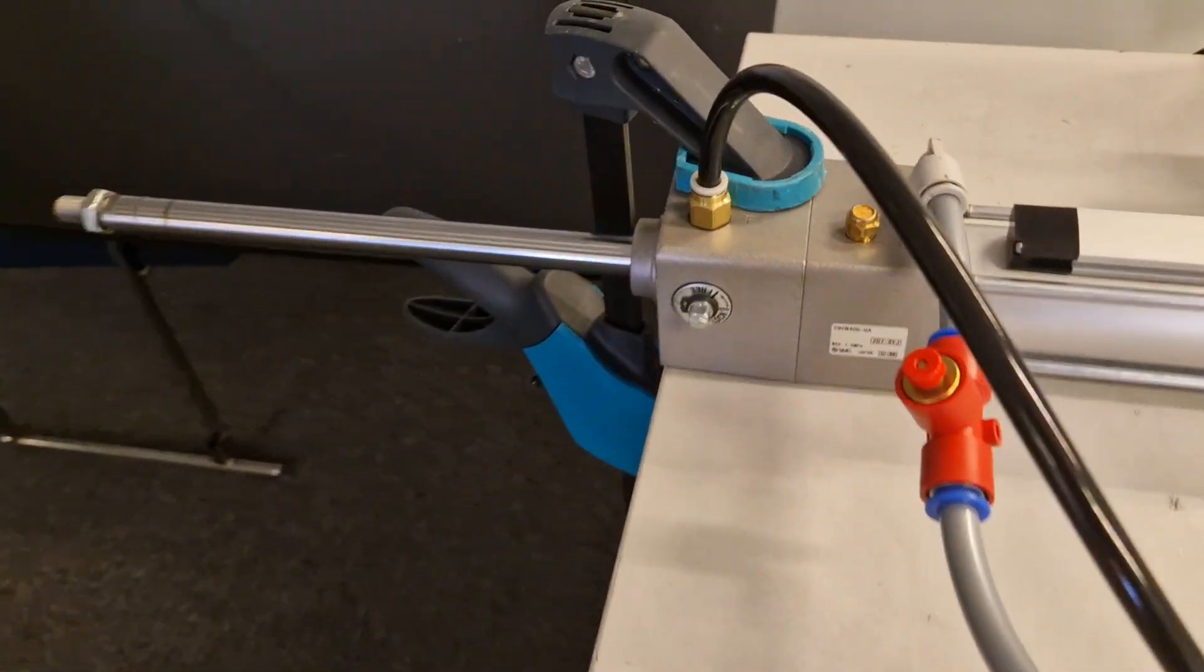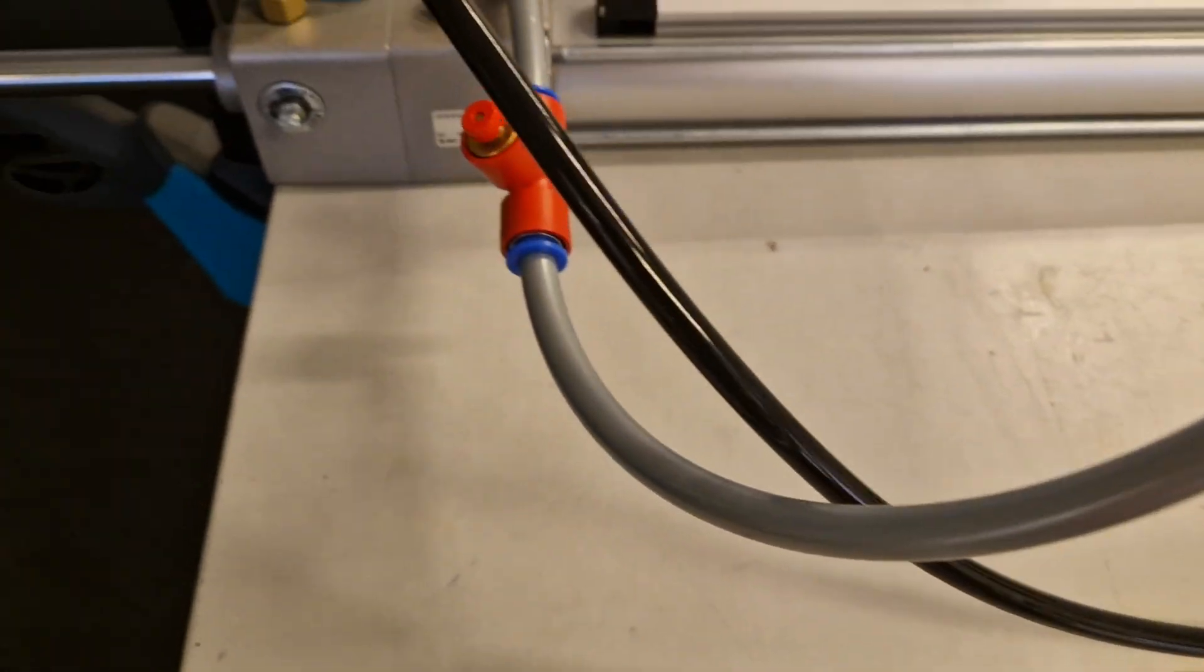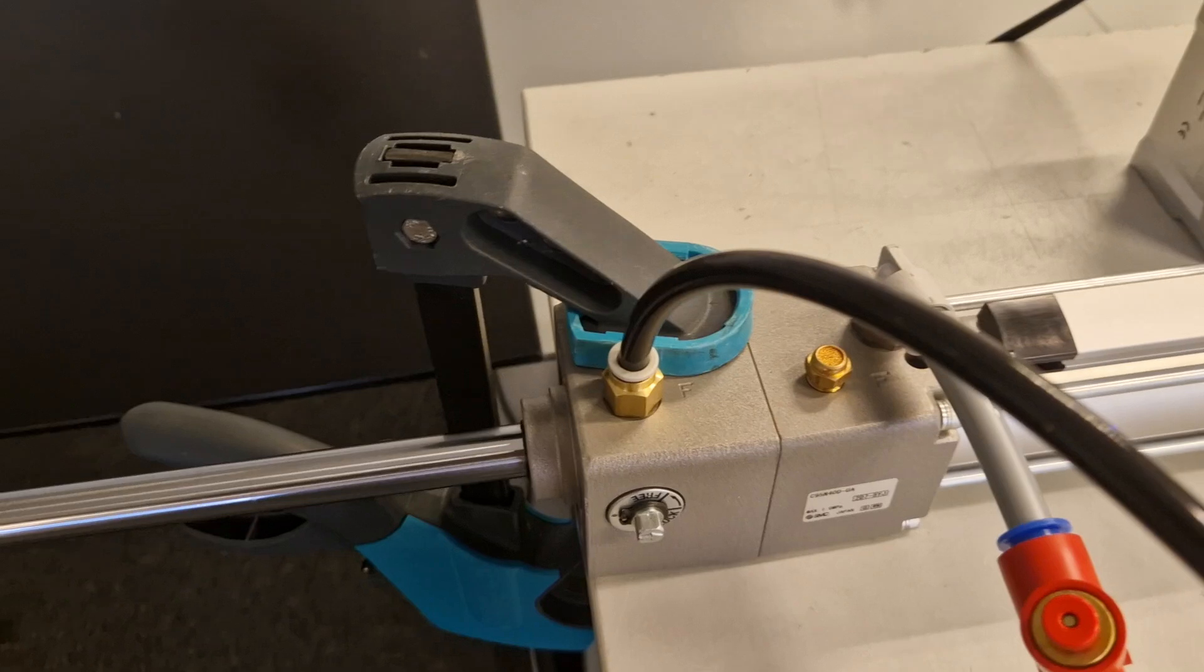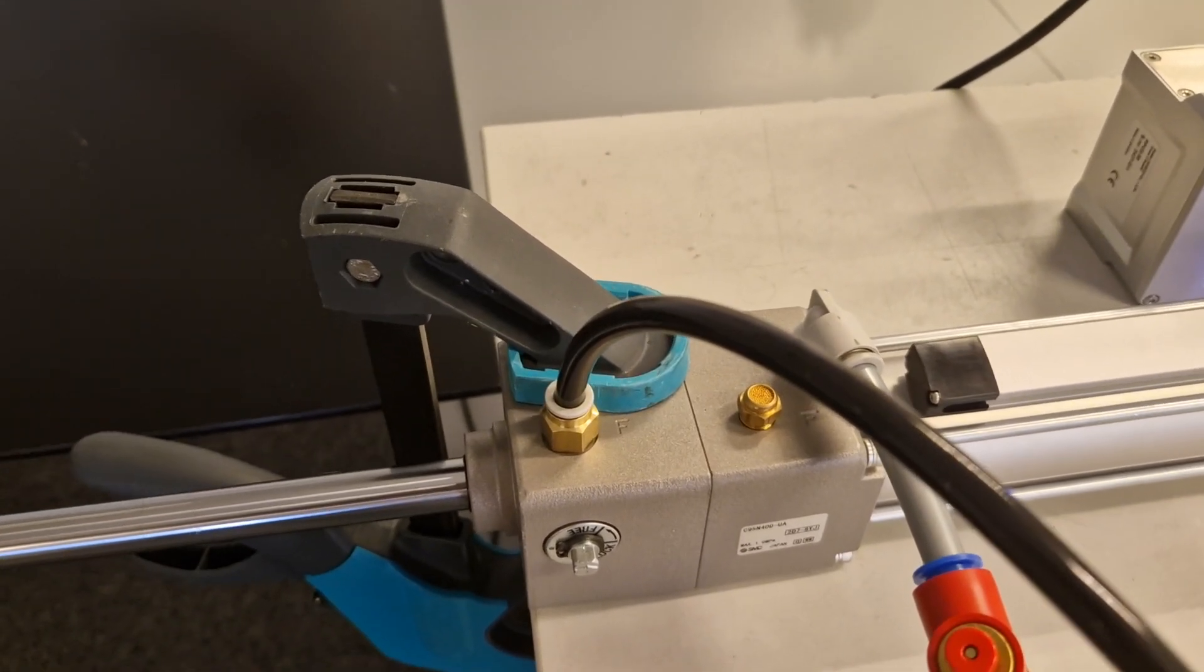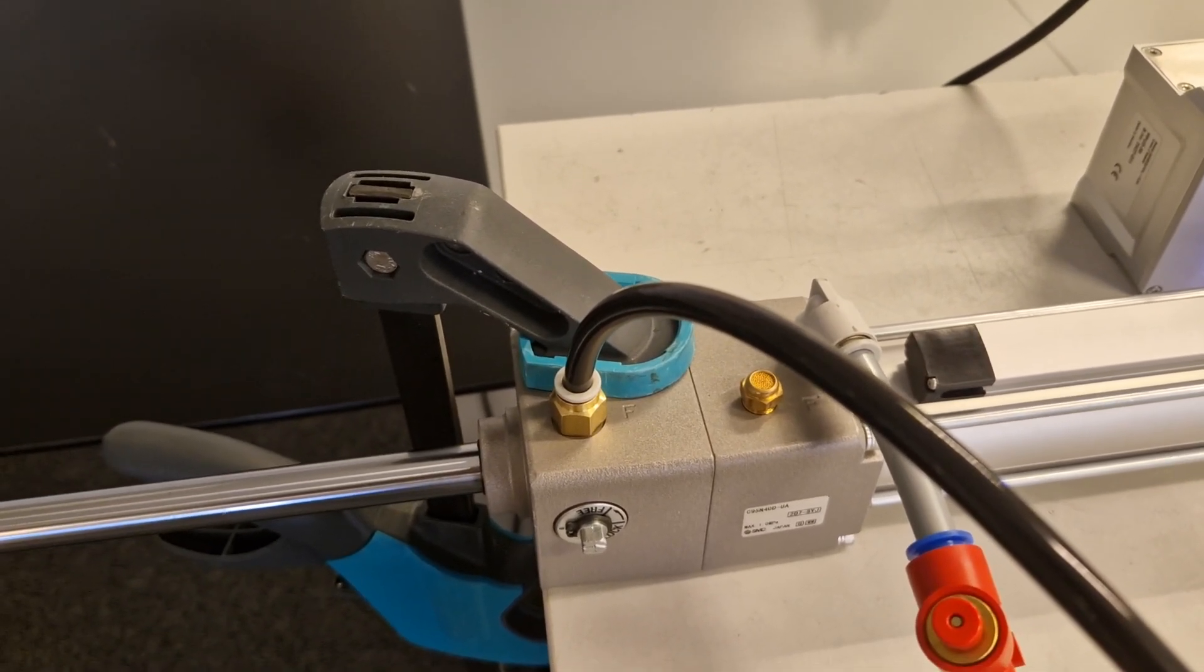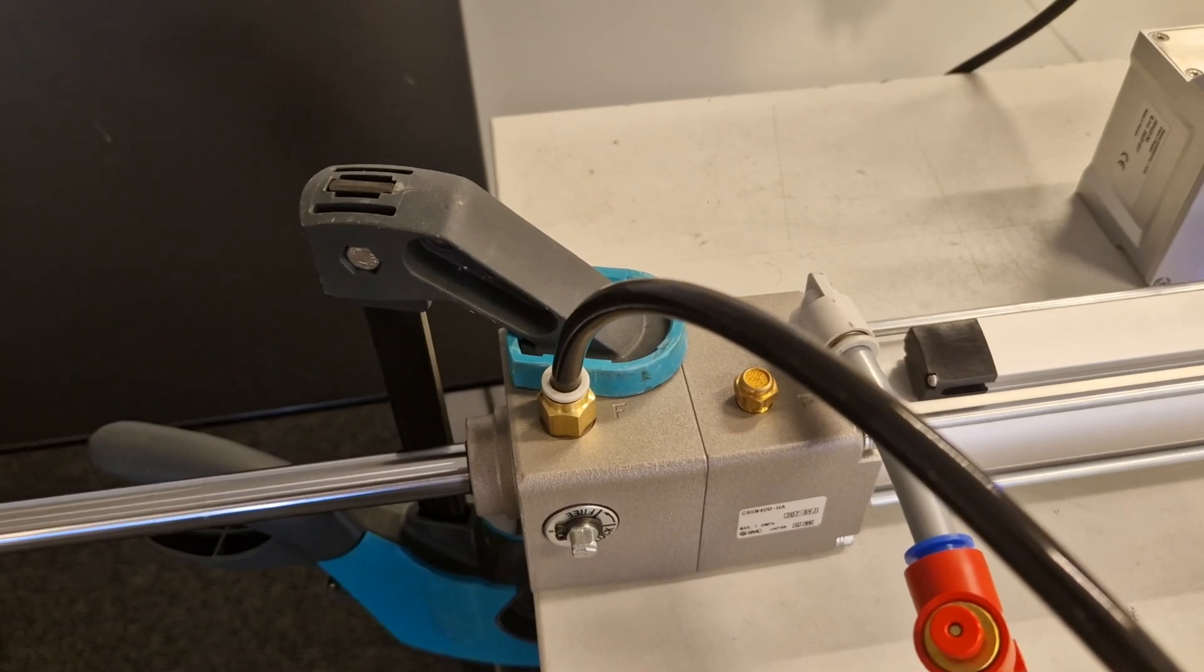Now you hear the noise from the valve exhausting the lock. When it's positioning, the lock is disengaged. As soon as it reaches its required position and it's happy with that, it stabilizes the pressures and locks the lock.